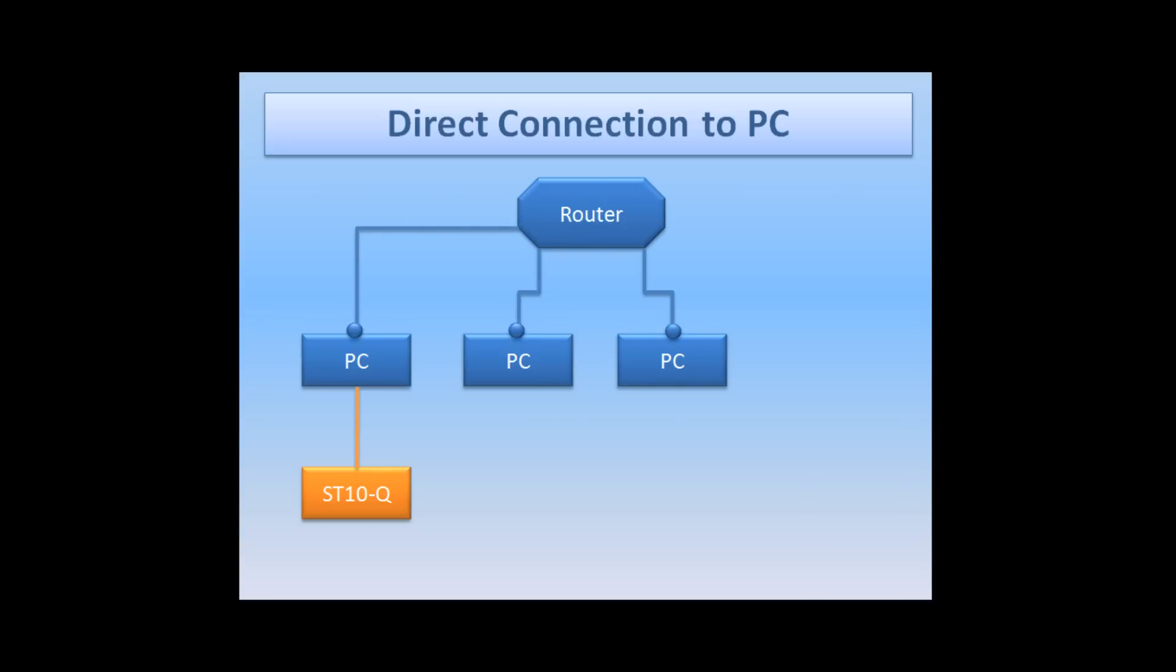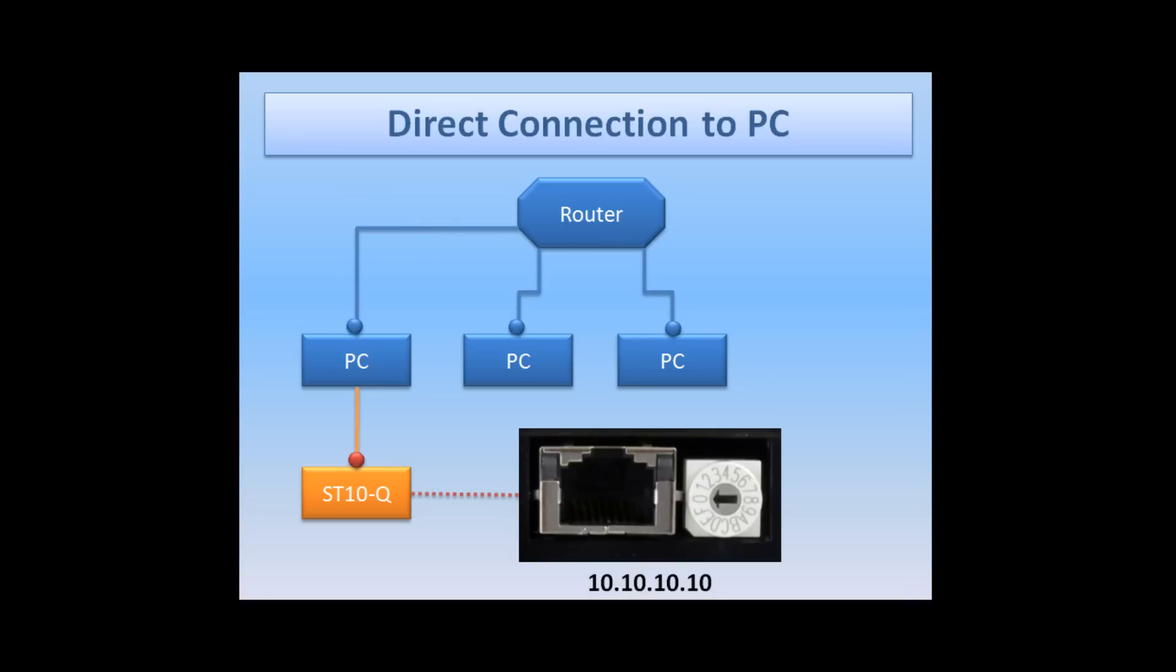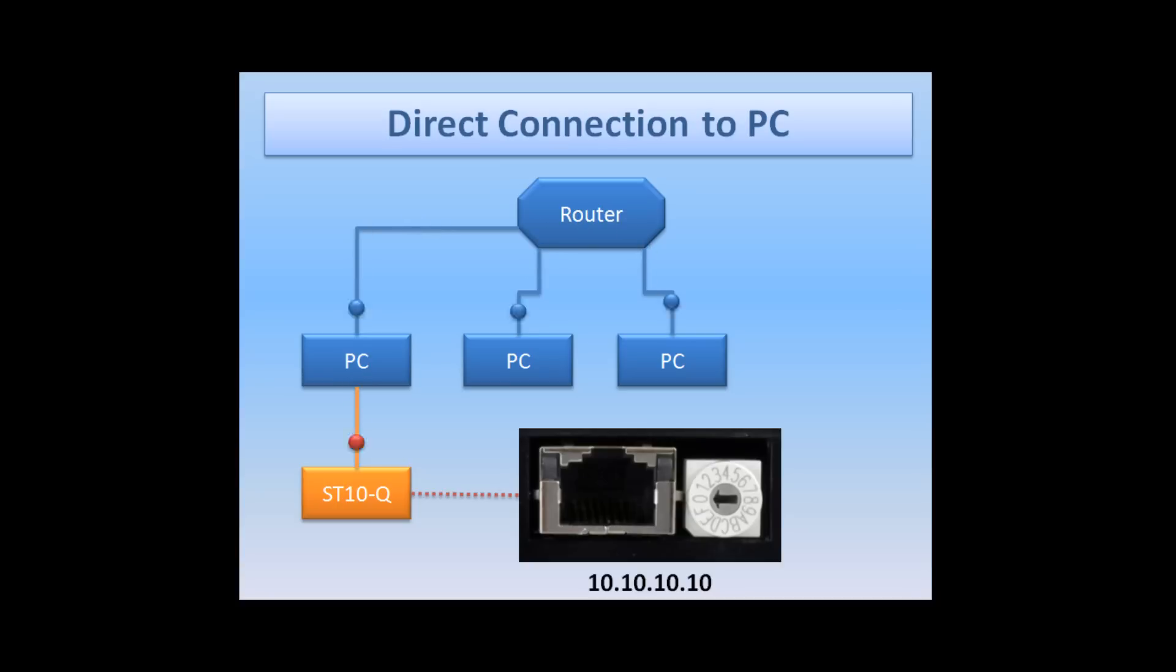To connect directly to a PC, set the rotary switch at position 0 so the IP address is 10.10.10.10. No other network is likely to be on that subnet. Next, set the static IP address of your network card to 10.10.10.11. Let me show you how.